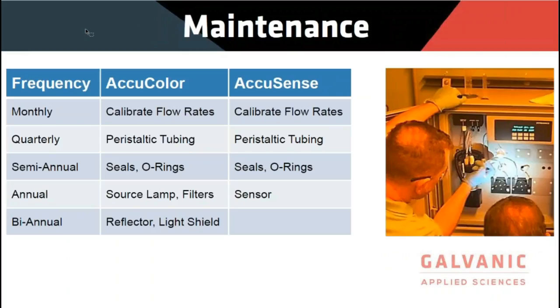Maintenance is very straightforward and minimal at most. For both systems, on a monthly basis, you'll want to calibrate the flow rates. Quarterly, you'll want to change out the peristaltic tubing, and then twice a year, check the seals and replace the O-rings. All this is included in our standard maintenance kit, so you don't have to worry about getting multiple parts. It's all within one part number.